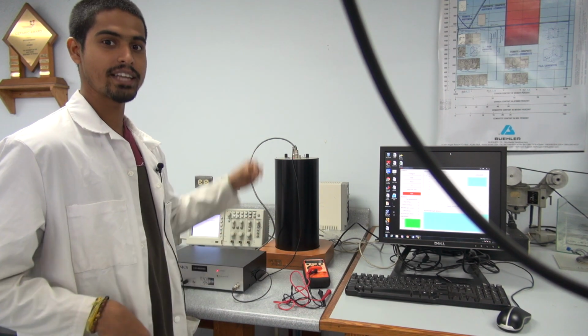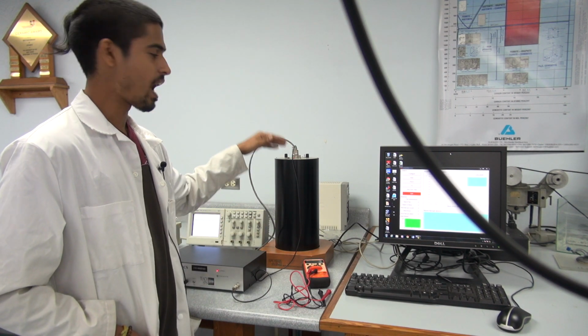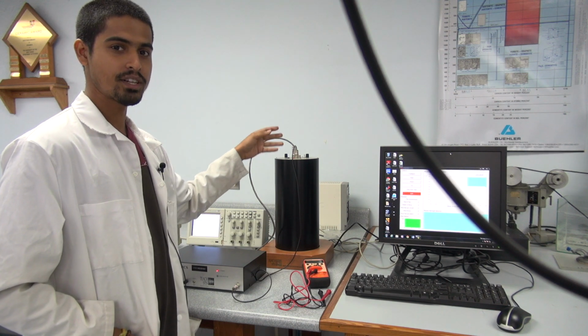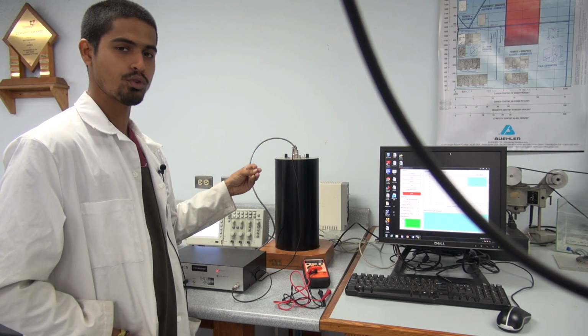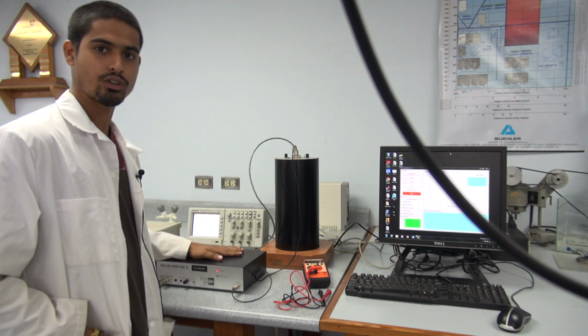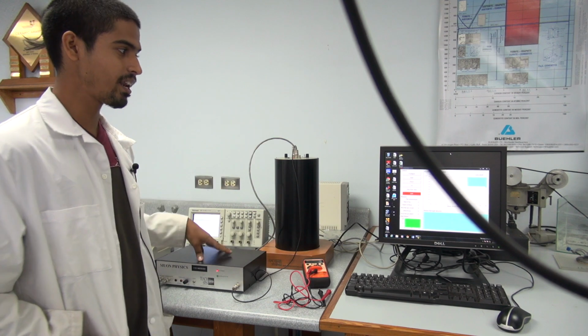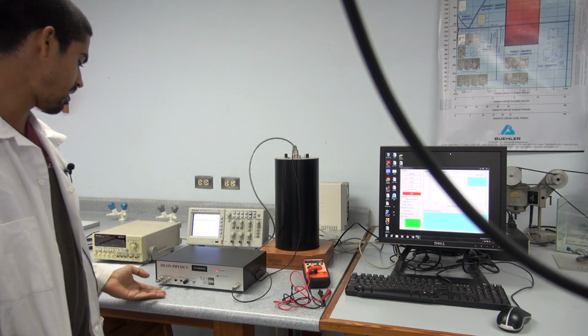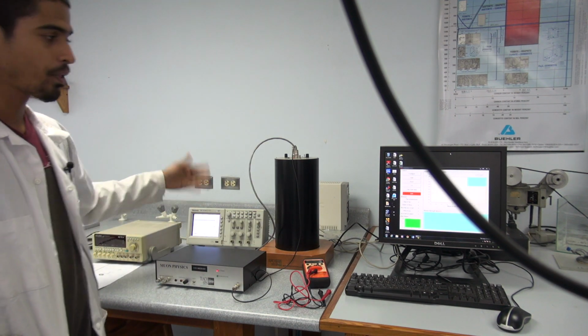That photon is detected by the photomultiplier tube. And the photomultiplier tube converts that signal from the photon into an electrical signal. And that signal is sent into our electronics box. And then from the electronics box to the amplifier and discriminator output you can see on the scope, and it's sent directly to the software as well.